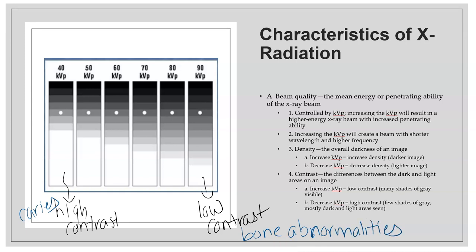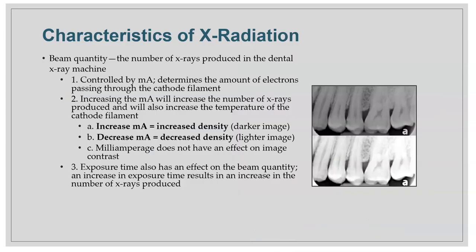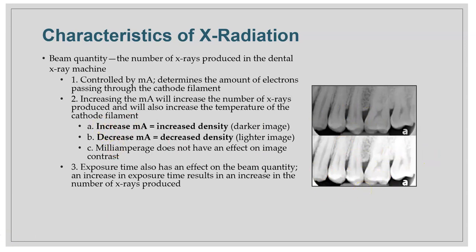With mA, increasing milliamperage gives a darker image. Think of baking a cake — increasing oven temperature darkens the cake. Decreasing temperature gives a lighter cake. Same with mA: decrease for lighter, increase for darker.